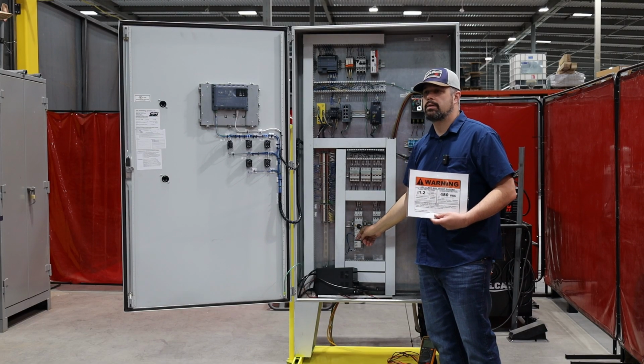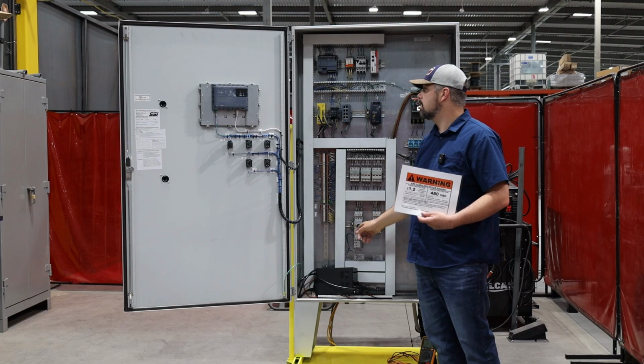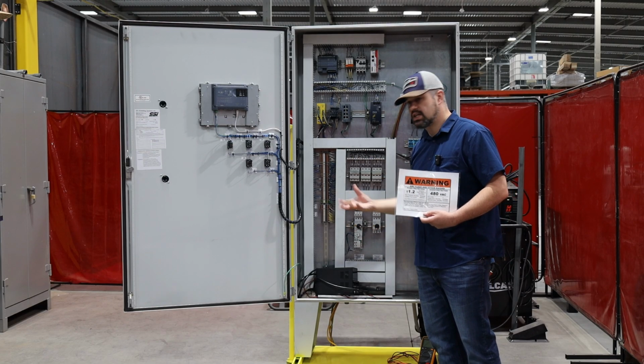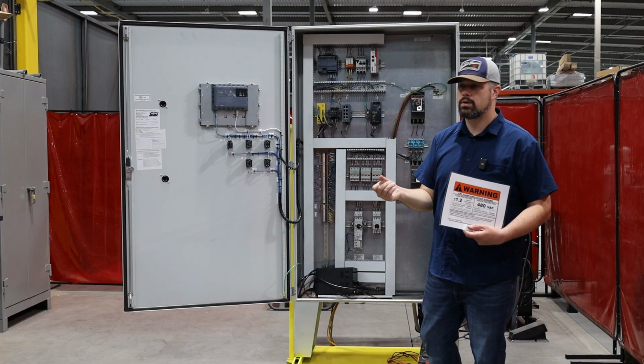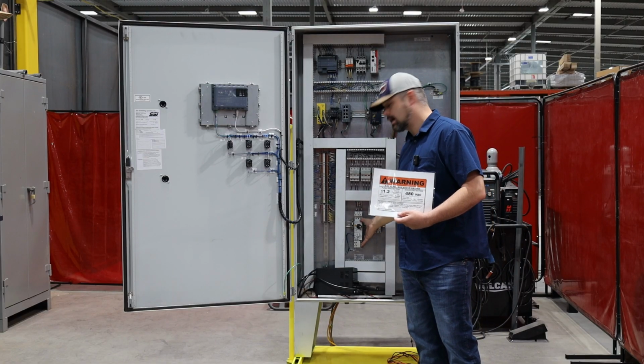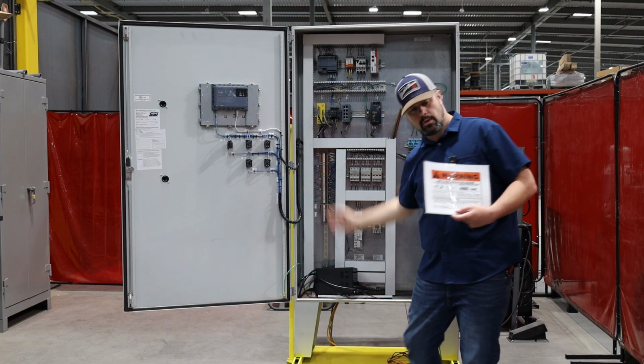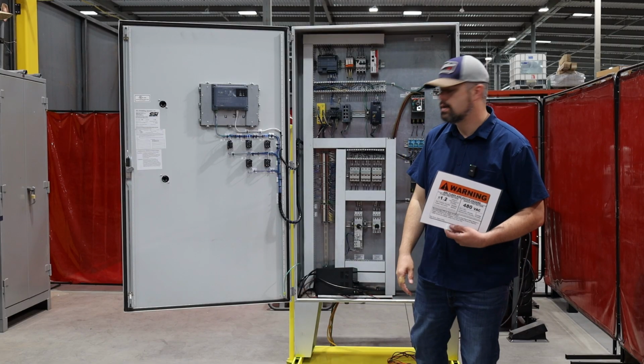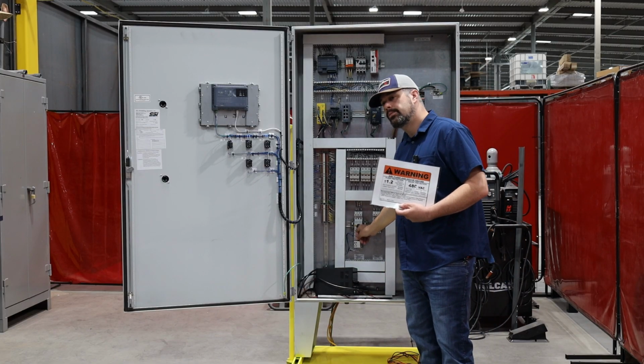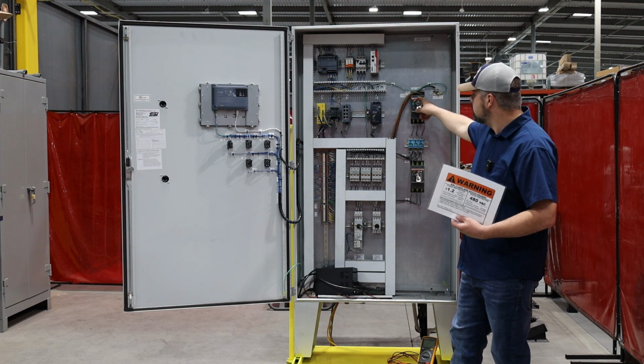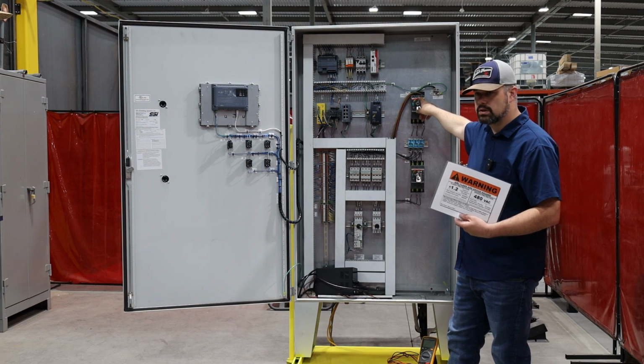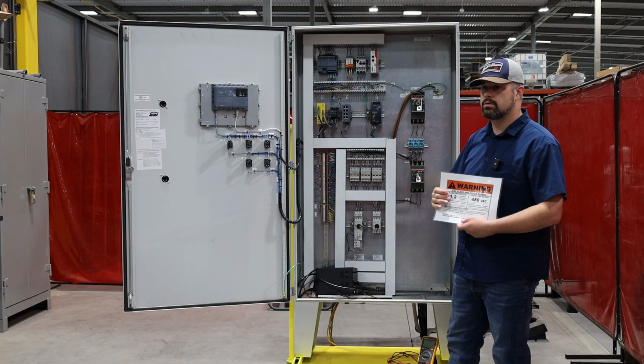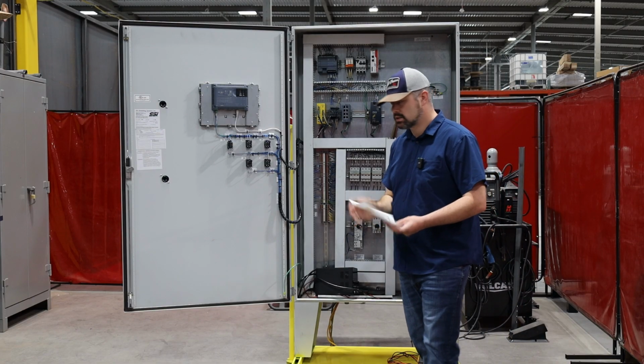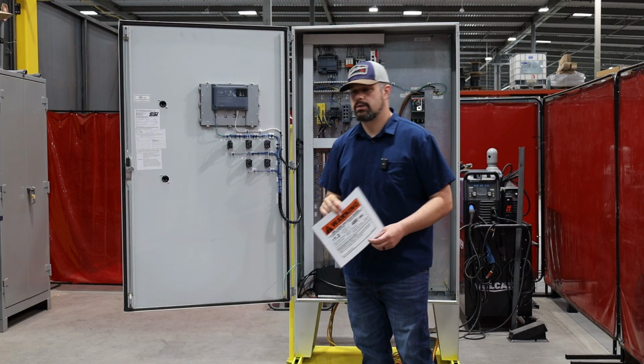24 volt, that's the 24 volt control circuit coming from the PLC, sucking in that relay in order to suck in the contactor and allow big 480 volts to flow to the motor and turn it on. Yeah, we could reseat a wire down here because we're further than 18 inches away from our exposed conductor, and we have to respect that 18-inch boundary. So you see what I mean when I say just a little bit of information.